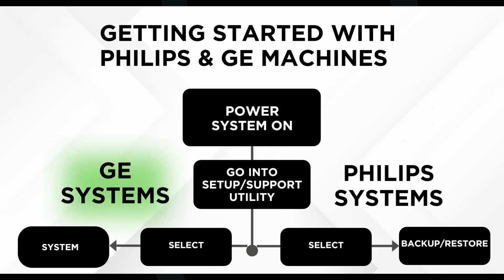Getting started with backing up Philips and GE machines. Typically, you would arrive on a site. If you need to make a backup, power on the system, you go into support or utility. For GE systems, you would go to the system tab, select backup restore. Make sure you use some type of backup media. Typically, all the newer systems use USB devices. Some older ones use CD-ROMs. I can go over through here.